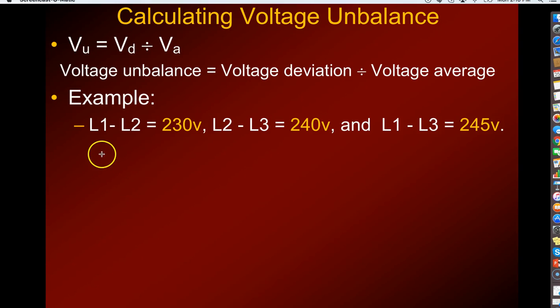You'll take your voltmeter and you will measure incoming power between L1 and L2. Now that's not a minus sign, that's just showing that you measure between L1 and L2. So in this example, you would measure and record 230 volts. Then you'll measure between incoming line 2 and incoming line 3, that's L2 and L3, and you read 240 volts. And then you'll measure across L1 and L3, and in this example, it's 245 volts.